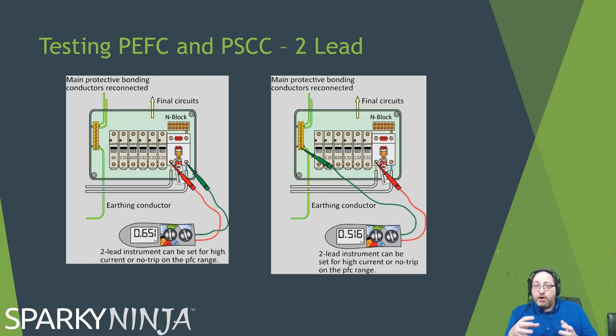It's likely that those parallels will offer a lowered resistance, which, thinking of Ohm's law, would result in a higher current, and you need to find out what the highest prospective fault current is. So we need to have all parallels reintroduced when we do this test. Alright. 2 lead, we have between line and neutral, that's the prospective short circuit current, and from line to earth, which is the prospective earth fault current. We measure both. As you can see here, 0.651 between line to neutral, 0.516 between line to earth, and they are in kA, so that's half a kiloamp. In this case, the prospective short circuit current of 0.65 kA will become the PFC of 0.65 kA. We just take the highest as the PFC.